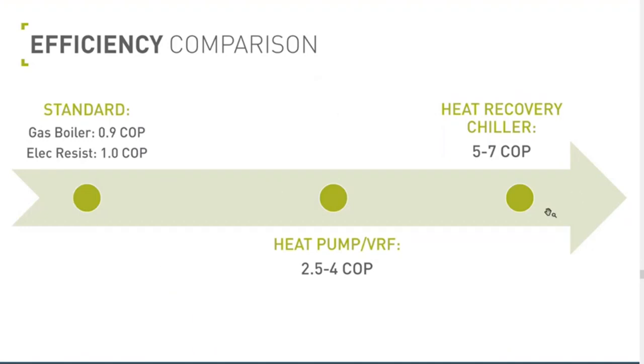Here's an efficiency comparison on a simple chart. A gas boiler operates at about 90% efficiency, maybe a little less. Electric resistance is about 100%. That VRF or heat pump or air source we talked about is anywhere from 2 to 4-ish, depending on your climate. And a water source system is anywhere from 5 to 7.